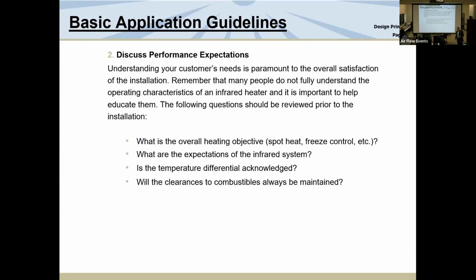I have a policy: if somebody orders an 80-foot long, 200,000 BTU heater, so that's our longest and our highest BTU, and it's just one heater, I make the customer get called. Not the rep, not the distributor, but the customer. Well, why are you buying one 80-foot heater? Well, my building's 100 feet long and I don't want to buy 2 heaters.